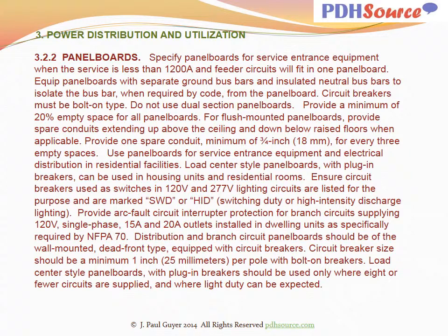With regard to panel boards, specify panel boards for service entrance equipment when the service is less than 1200 amps and feeder circuits will fit in one panel board. Equip panel boards with separate ground bus bars and insulated neutral bus bars to isolate the bus bar when required by code from the panel board. Circuit breakers must be bolt-on type. Do not use dual section panel boards. Provide a minimum 20% empty space for all panel boards.